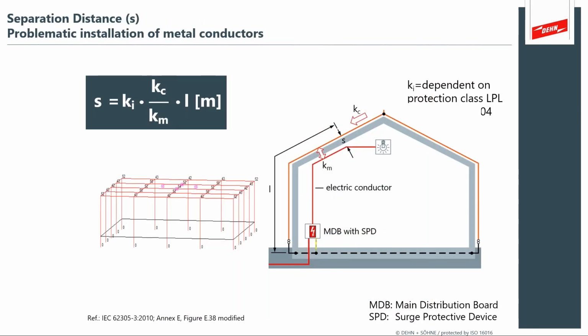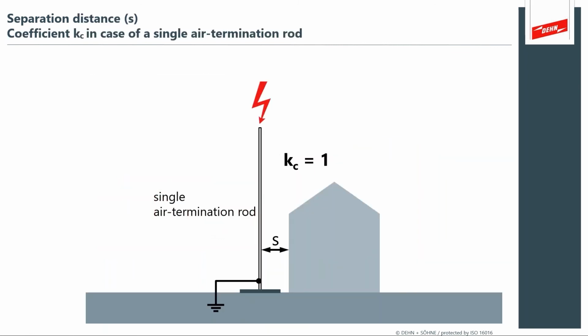So now we move along to separation. If you can't bond it, you have to separate from it. So in your lightning protection system, the IEC standard dictates what's called the separation distance, S. And this is intended to provide separation to avoid side flash. If this building is struck by lightning and it enters into the down conductor system, you do not want the side flash into your adjacent electrical systems. So back to the concept of either bond it or separate from it.